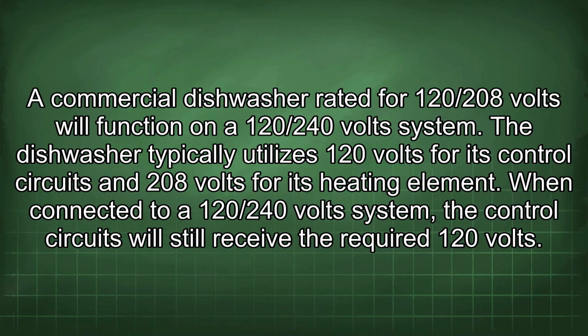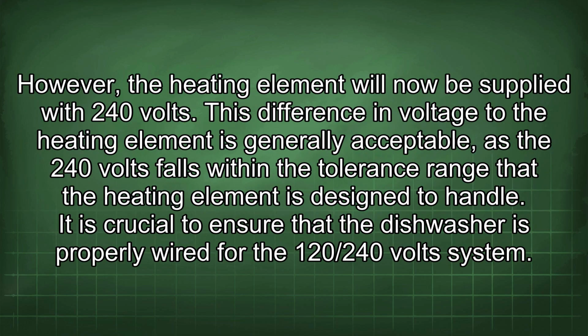A commercial dishwasher rated for 120/208 volts will function on a 120/240 volts system. The dishwasher typically utilizes 120 volts for its control circuits and 208 volts for its heating element. When connected to a 120/240 volts system, the control circuits will still receive the required 120 volts. However, the heating element will now be supplied with 240 volts. This difference in voltage to the heating element is generally acceptable, as the 240 volts falls within the tolerance range that the heating element is designed to handle.